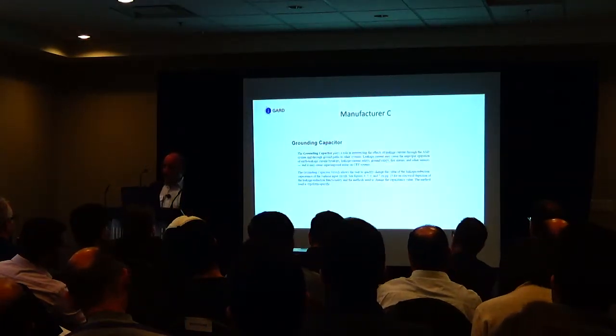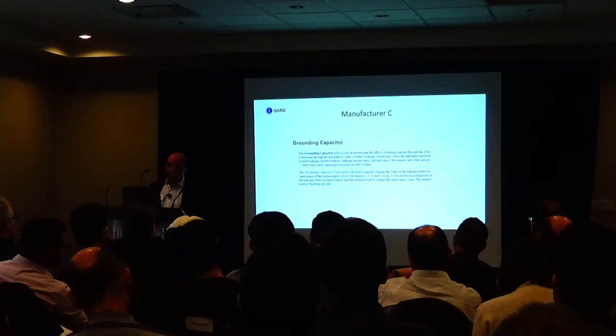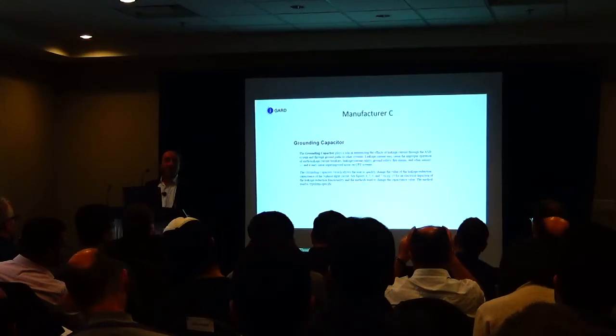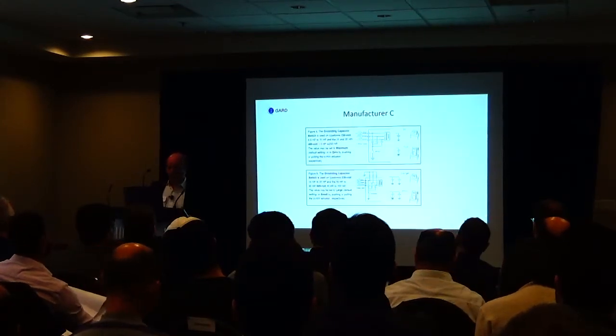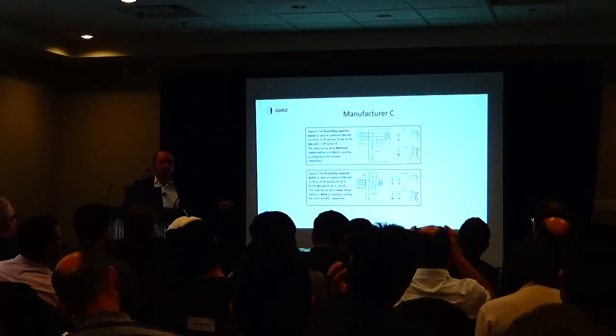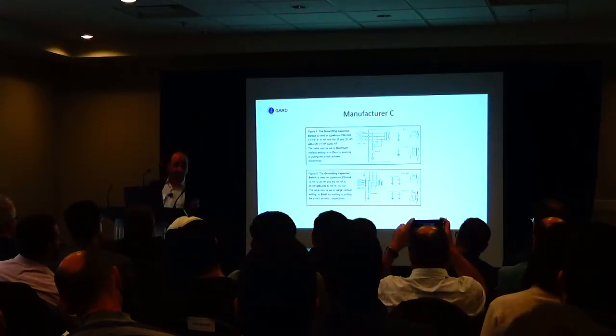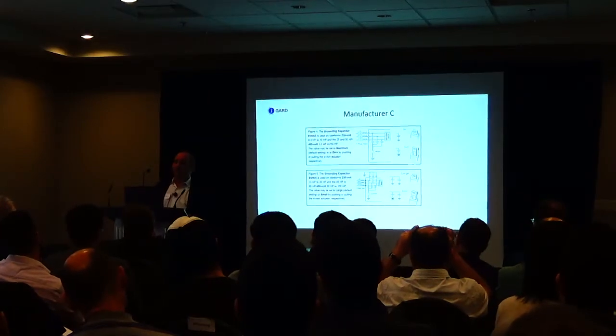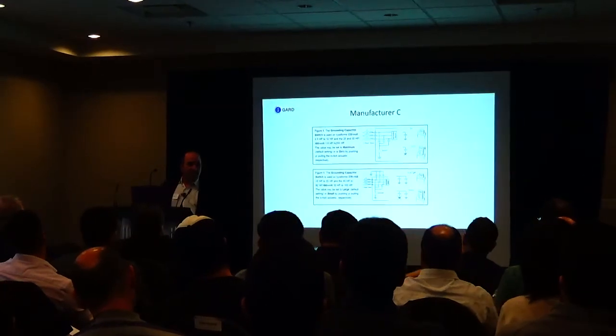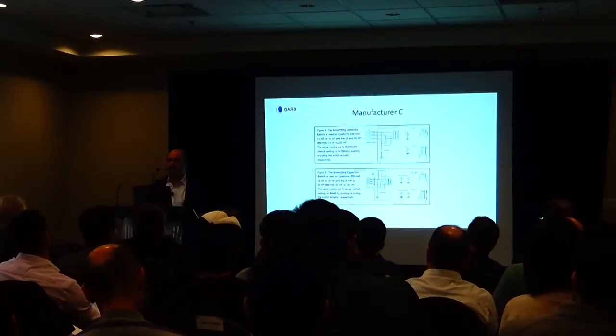A grounding capacitor switch allows the user to quickly change the value of leakage reduction capacitance of a 3-phase input circuit. See figures 4, 5, 6, 7, 8, 9 on page 19. It's all clear now, right? So we look at the figures. That's the switch there. What we did is we moved the capacitance. Because variable frequency drive manufacturers think that, well, and UPS manufacturers think that ground is this infinite, miraculous place where all unwanted frequencies can go. Right? When you have a variable frequency drive, you have pulse width modulation, you need to filter out that stuff someplace, send it to ground.